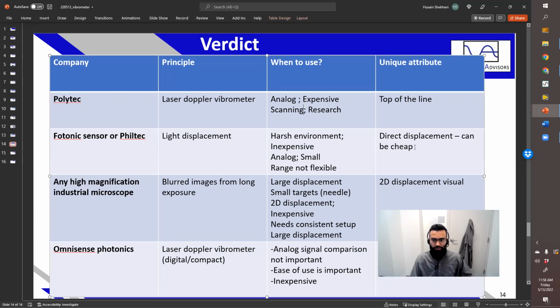If you want cheap light displacement measurement, I would say the Philtec device is the right one. If you want direct displacement, you want analog, that's another part. If you want analog light displacement, a direct measurement, then that would be the one for you. If you know you have large displacement and you're measuring it like in a water chamber, or you need something that's relatively inexpensive, you just want to verify that things are oscillating, then I think the high microscope camera will work well.